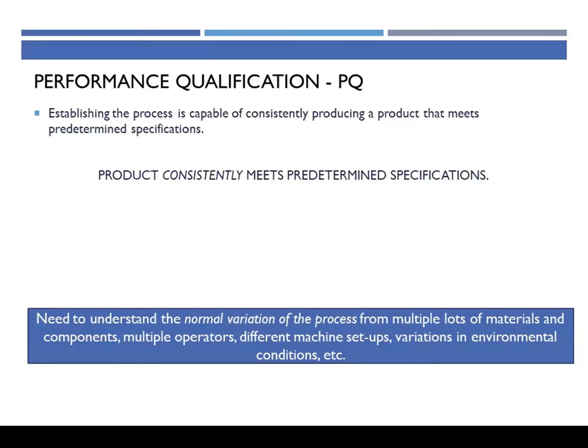So what we're going to do is rigorous testing for the PQ, and we're going to run at nominal settings now. And we're going to do repetitive testing, probably at least 3 or more batches. We're going to try and simulate some of that variation. And now don't try to play games here and think, well, if I have to run 3 batches, that's a lot of work, so I'm just going to make them teeny-weeny little batches. That's not acceptable. That's not good for you because you don't know what your variation is. That's not good for your customers because they're taking all the risk of getting a bad product. And the FDA is going to figure out that you're playing games. So don't. Make at least 3 or more batches.